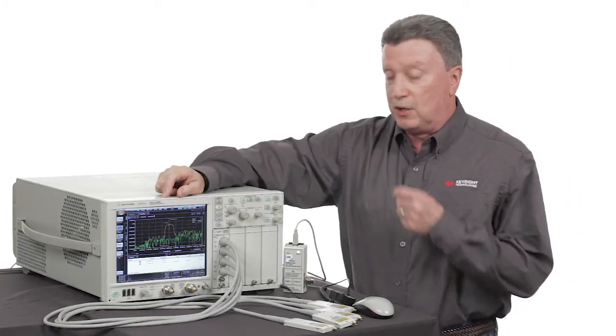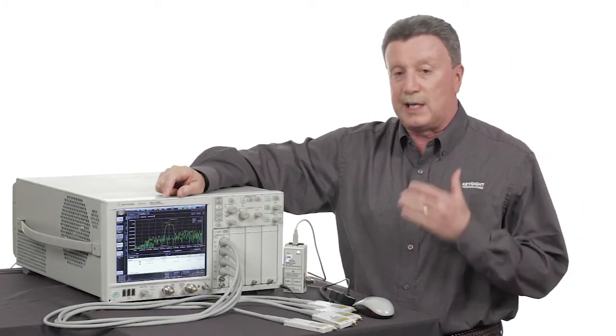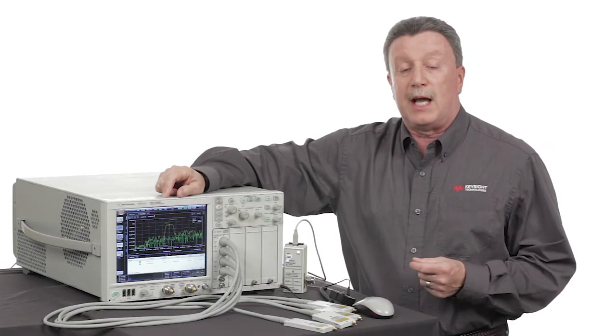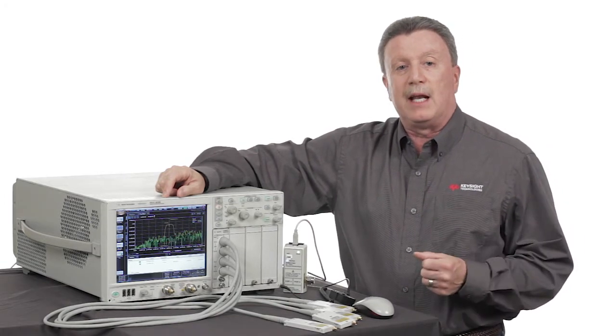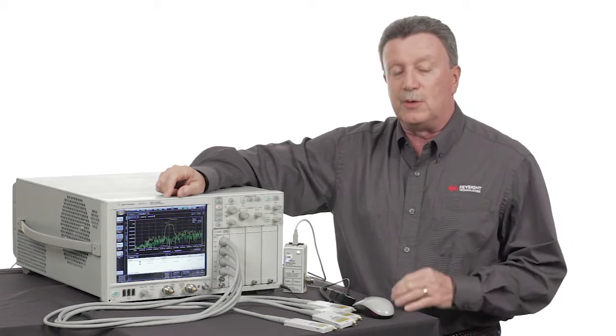Now an important note is you can use the TDR to make measurements without calibration, but to maximize accuracy like we want to do today and to take advantage of advanced features like de-embedding and AFR, you need to do a calibration.